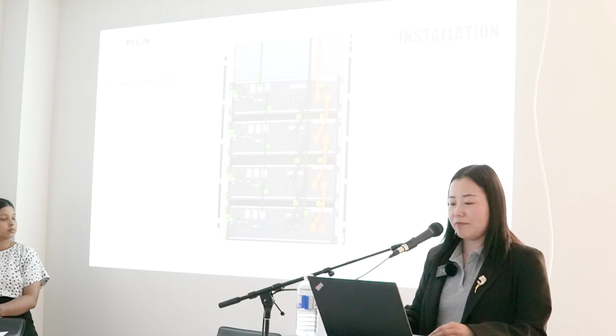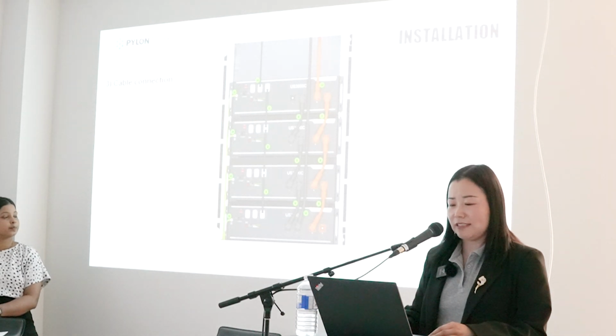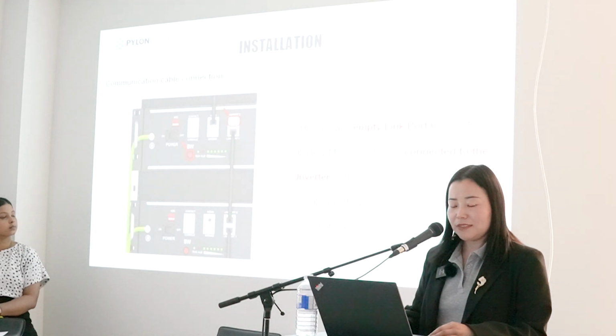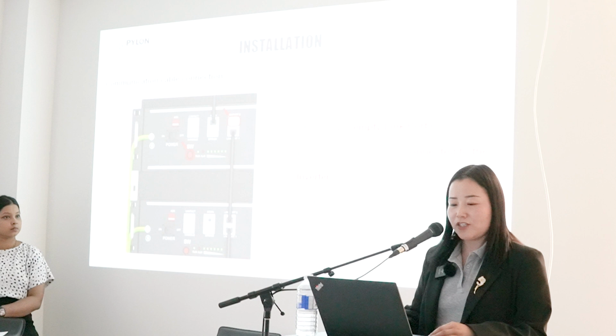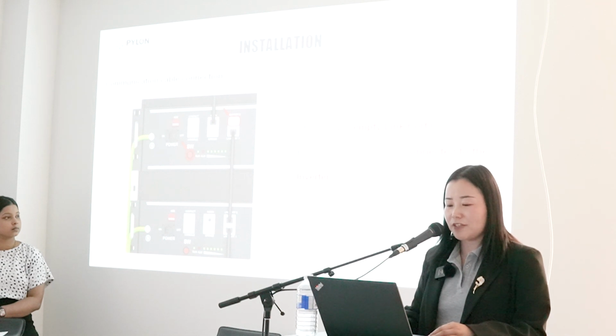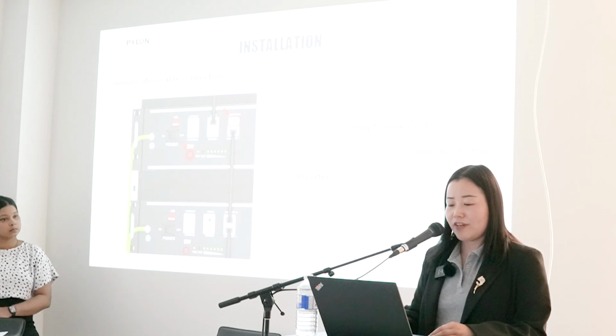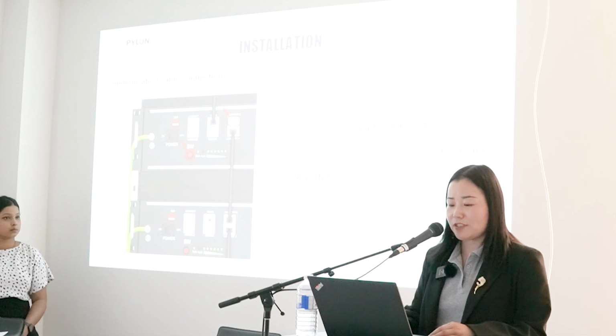Batteries are connected in parallel. So link 1 of the first battery connects to link 0 of the second battery. Power cables connect to the inverter, and a CAN or RS485 port of the master battery connects to the inverter. Every battery has to be grounded. So this communication cable connects here. The one with empty link port 0 is the master battery module, which is connected to the inverter. Others are slaves. One master battery with a maximum of 15 slave batteries in one string.